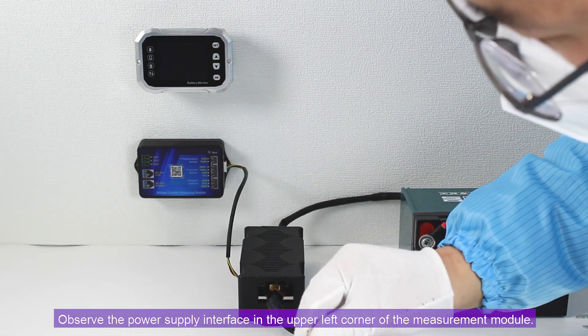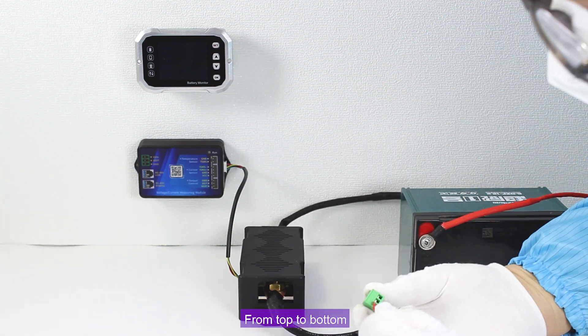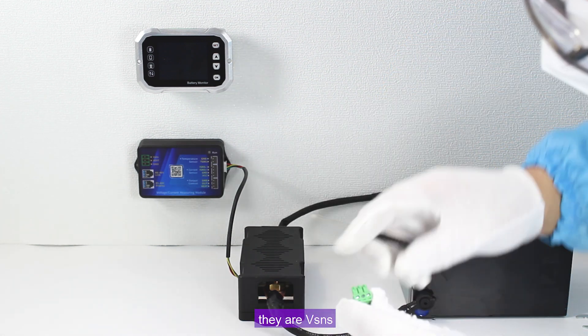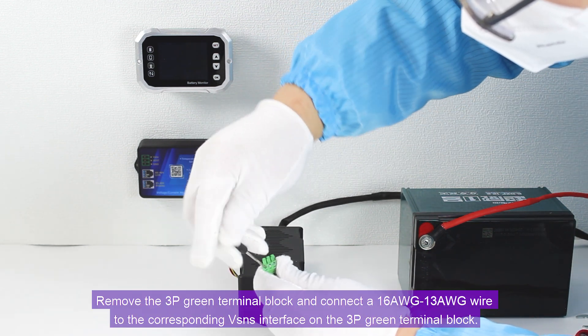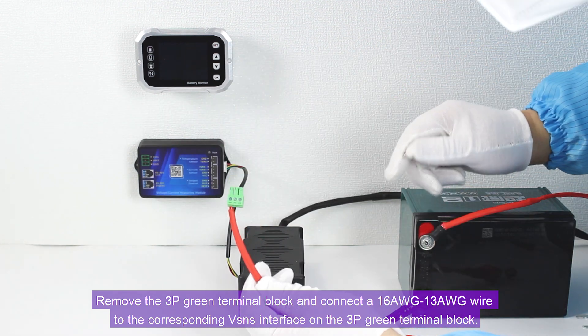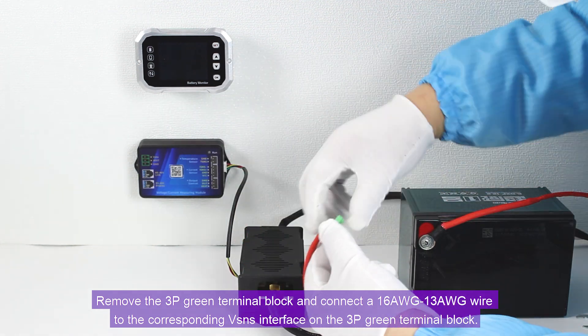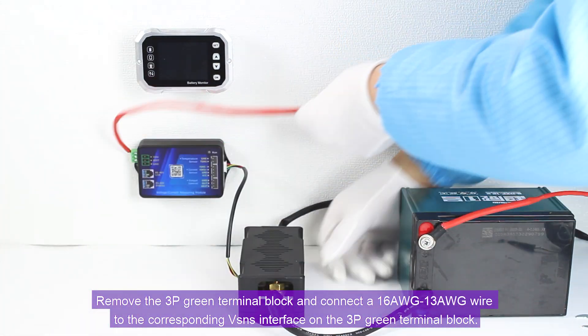Observe the power supply interface in the upper left corner of the measurement module. From top to bottom, they are VSNS, VEXT, and GND. Remove the 3P green terminal block and connect a 16AWG to 13AWG wire to the corresponding VSNS interface on the 3P green terminal block.